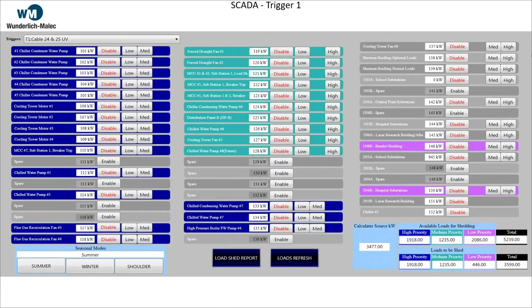So if you take a look at the lower right corner, you'll see where everything's being calculated, such as what's available for your high priority loads, medium and low, and so forth. If you want to go on to the next slide, we'll show you what happens when an event happens. So here's our load shed reports, and just this little screen quickly shows that trigger one happened, the utility loss. It shows what was available and what was actually shed. The next screen will show the actual report. And one thing that our customers have told us is that they do have different load shed systems in place, and it often takes them a long time to figure out what happened, even if a load shed properly took place and they maintained their plant.